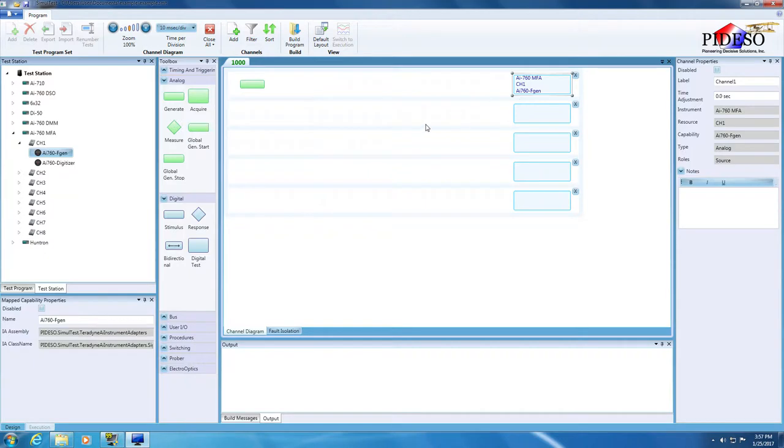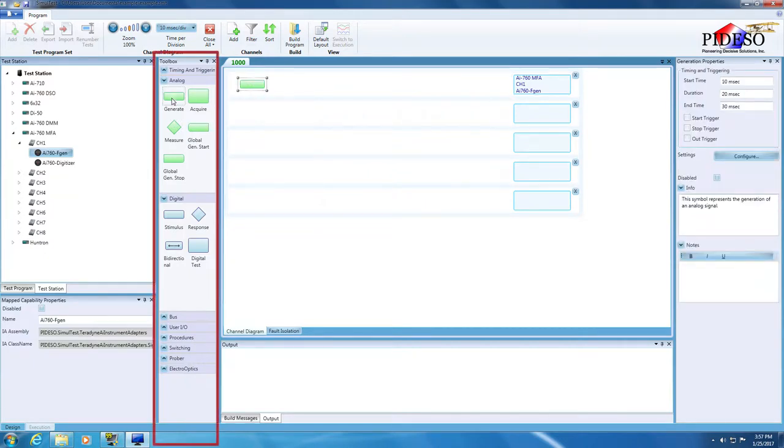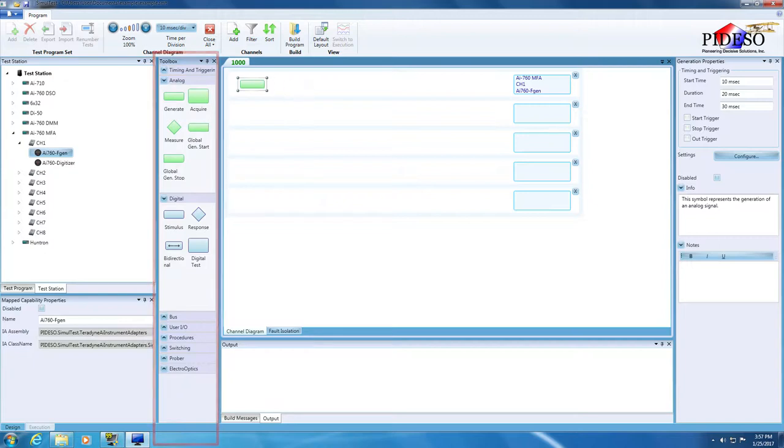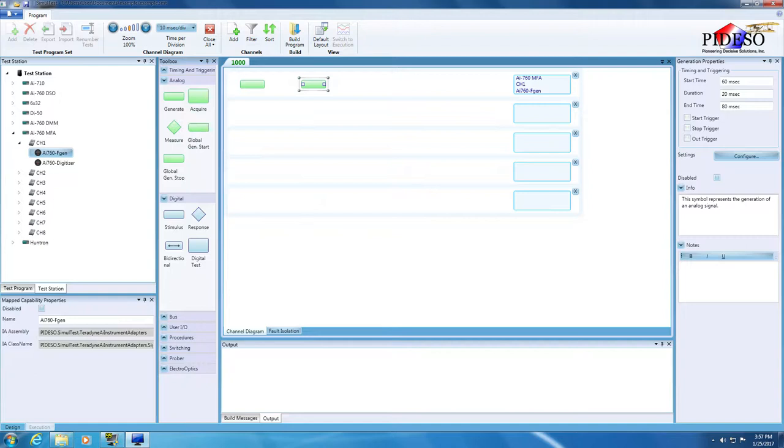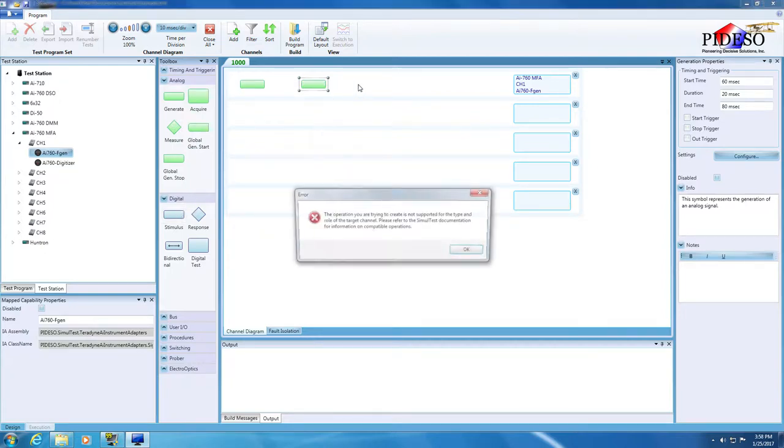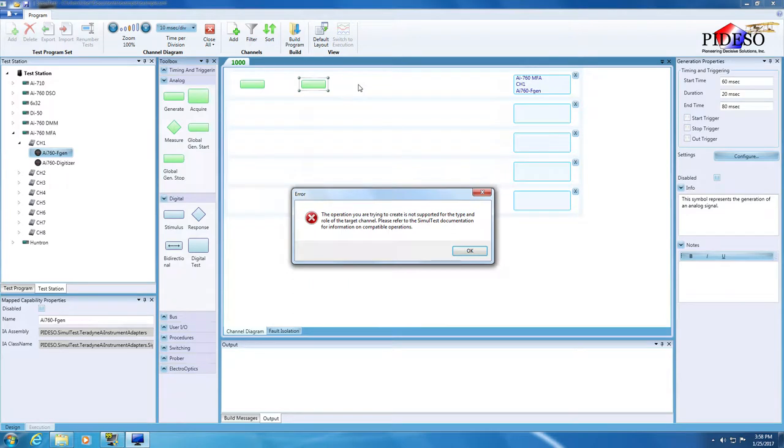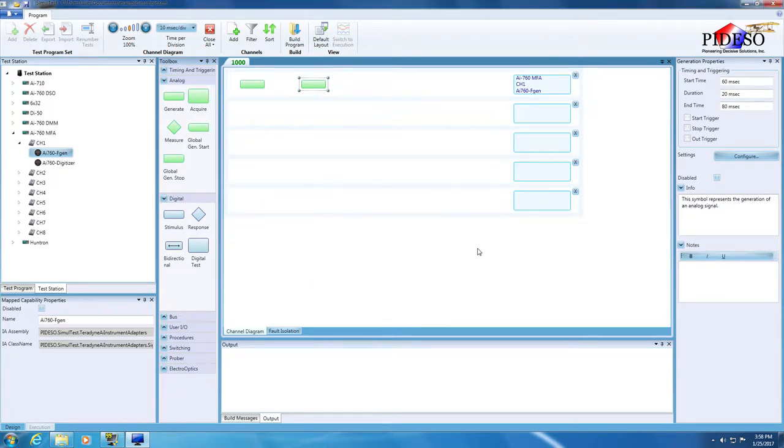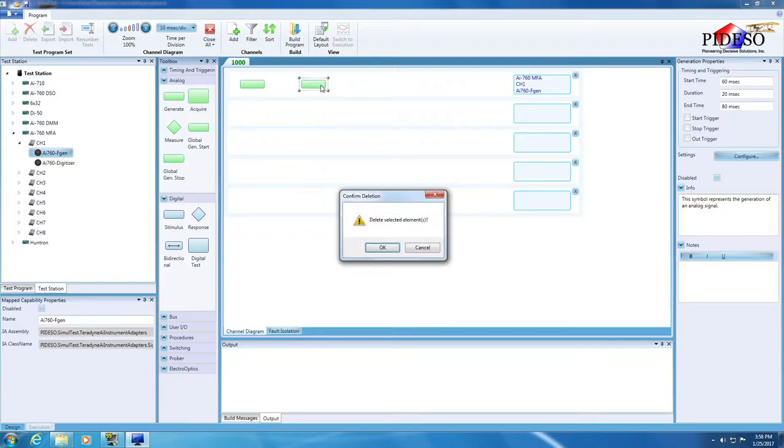To add another operation to this channel, simply pull another generate signal symbol from the toolbox. Since the assigned capability is analog and has a source role, the operation created on this channel is an analog generation. Only operations that are compatible with the assigned test channel capability can be dropped onto the channel. As you can see, I raise an error when I try to add in a digital operation from the toolbox. I don't need the second operation I brought in, so I'll select it then press delete on the keyboard to get rid of it.